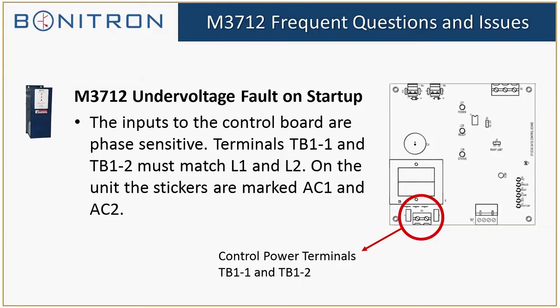Okay. All right. So the M3712 is our single phase power supply. Its purpose is basically to be an oversized front end for the drive, because if you want to use a three-phase drive on single phase power, you have to either double the size of your drive or seriously derate it. So a way you can save a little bit of money is to use a standard three-phase VFD and just use our single-phase power supply to replace the front end and power the drive through the DC bus.